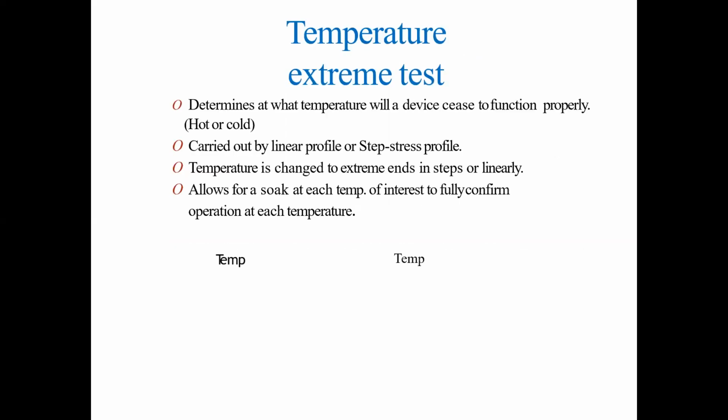So here, the temperature extreme test determines at what temperature a device will cease to function properly, hot or cold. It is carried out by a linear profile or step stress profile. Temperature is changed to the extreme ends in steps or linearly, which allows for a soak at each temperature of interest to fully confirm operation at each temperature.